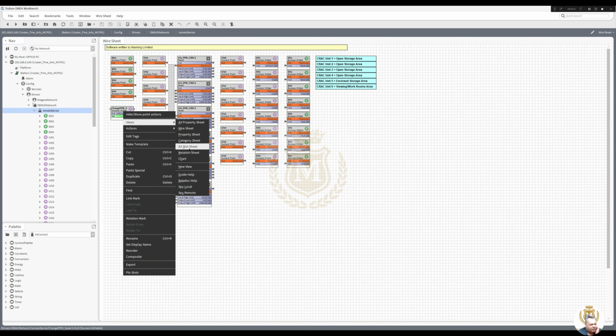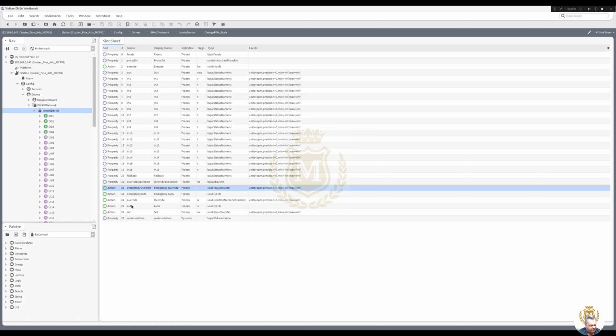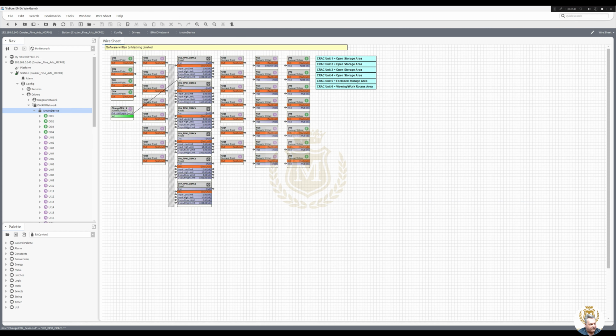So put that to a 0 so there's no decimal place, and then we'll select concentration and we'll select ppm. Save that. I think while we're in there, we'll right click, views, we'll do the AX slot sheet, we highlight emergency and auto, press my shift key and then click there, and then config flags, and we'll hide them so you can only see the set. And then we can move that to that 1000 there, and then all I need to do when I'm on site commissioning is, depending on what it's set at, I can just change that and they'll all work the same.